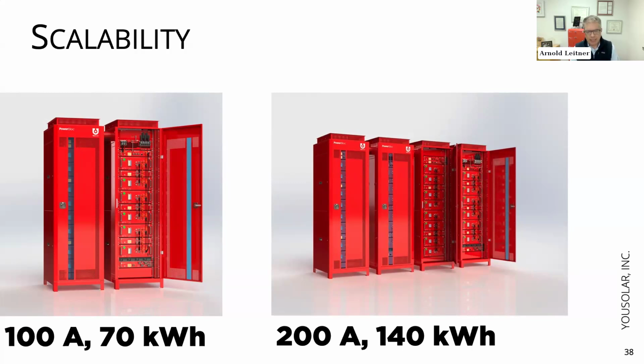For example, if you have a 10 kilowatt hour battery that cycles solar energy as it should, it's on average 50% full when an outage hits—that's 5 kilowatt hours of storage. With a minimum household load of 500 watts, in 10 hours your battery is dead. But the time between an evening, an overcast day, and another evening can be 36 hours, so there's nothing to recharge it and you know you're going to run out of power. For that reason, we don't provide a PowerBloc with less than 70 kilowatt hours of storage.